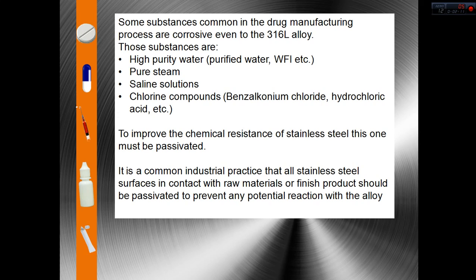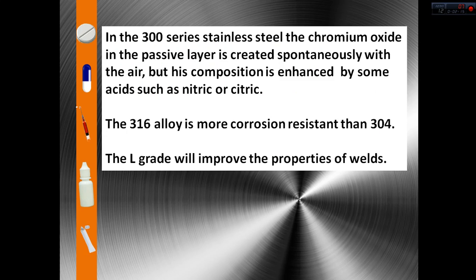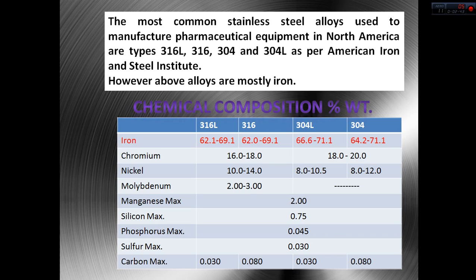One of the ways to get the best corrosion resistance from stainless steel is passivation. In the 300 series stainless steels, the chromium oxide in the passive layer is created spontaneously with air, but its composition is enhanced by acids such as nitric or citric. The 316 alloy is more corrosion resistant than 304, and the L-grade will improve the properties of welds. No matter if we have 316L stainless steel, that alloy will still have a lot of iron — at least 62%, as we can see in this chart.